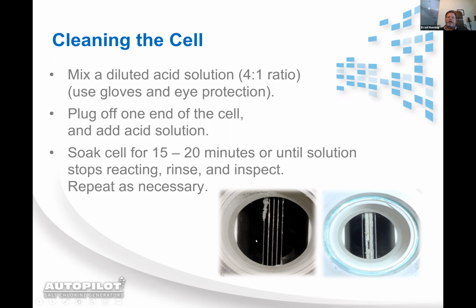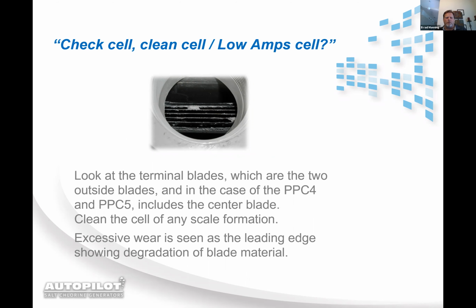The other thing you want to look at, like I said, now this is a smaller cell, so it's only got 5 blades. The left and right one, you want to look for depletion. But on a PPC5, it's got 15 blades in it. So you'll check the left one, you'll check the right one, and then you'll check the center blade to see if you notice any height difference or thickness in the cell blades. Once again, that's a sign of depletion. This is just going over what I was telling you earlier about which cell blades you want to check.